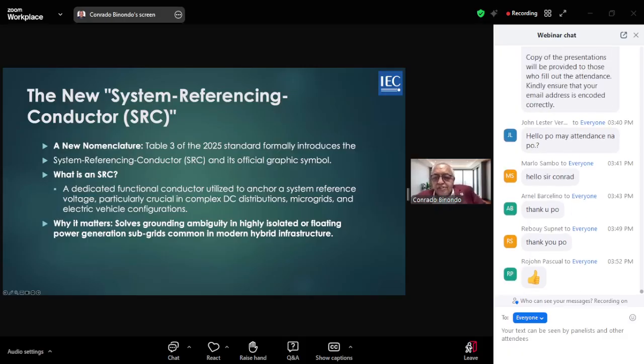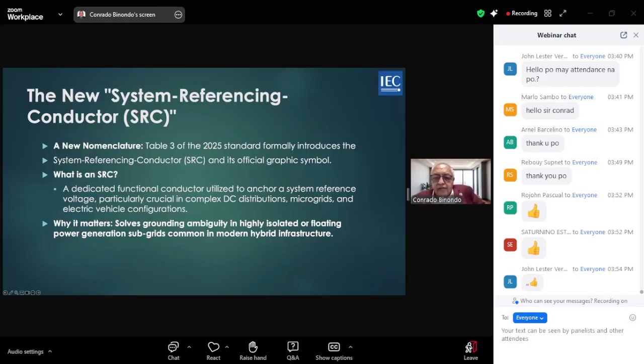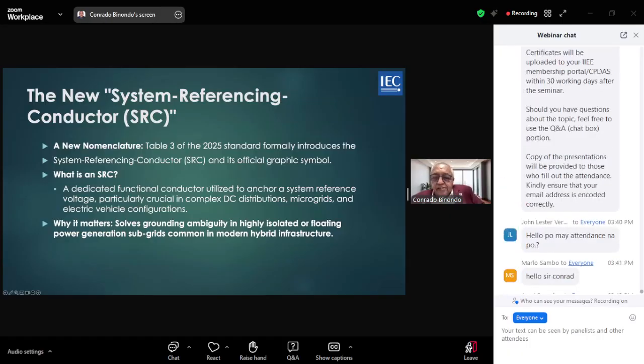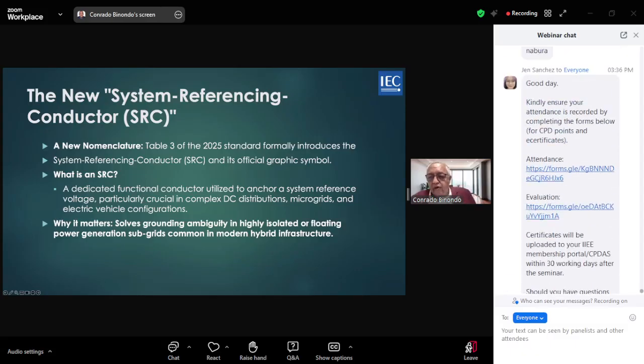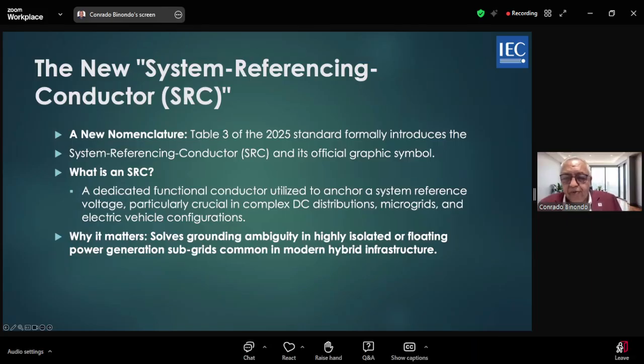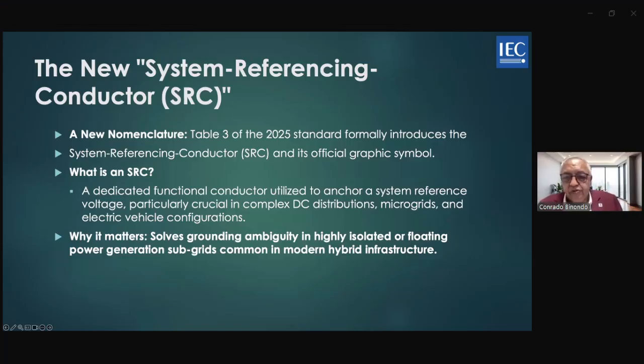So the introduction of the system referencing conductor in this standard is a nomenclature update driven by multi-source AC-DC microgrids and prosumer systems. The technical distinction is that in standard AC systems we use neutral N or PEN, but in a DC system we use a midpoint or line conductor. So the SRC serves as the overarching term for any conductor that intentionally connects a circuit's active reference point to the earthing system, to stabilize the voltage to earth.